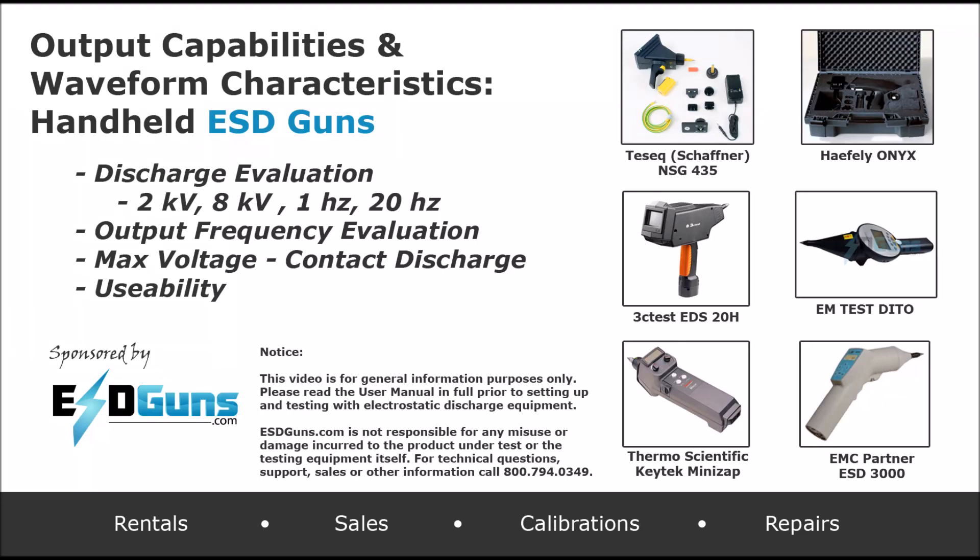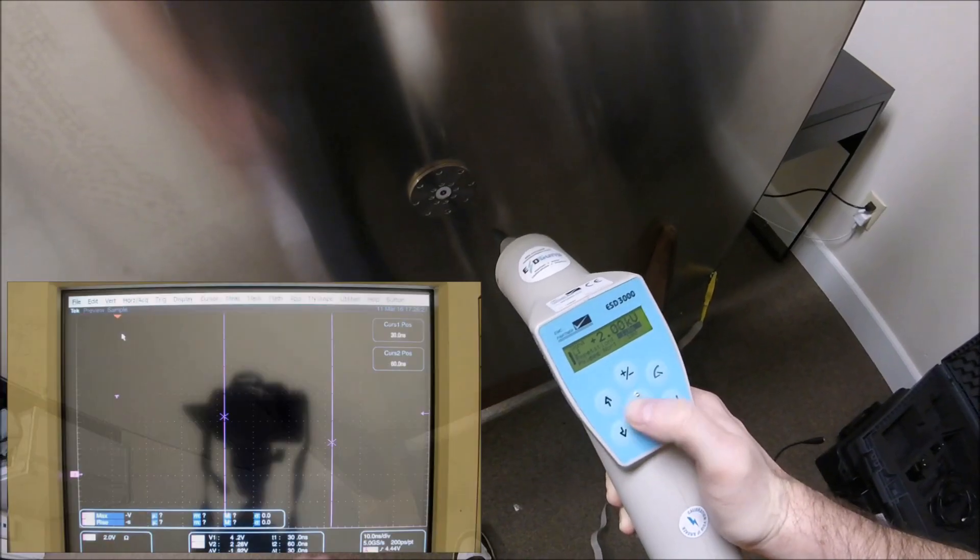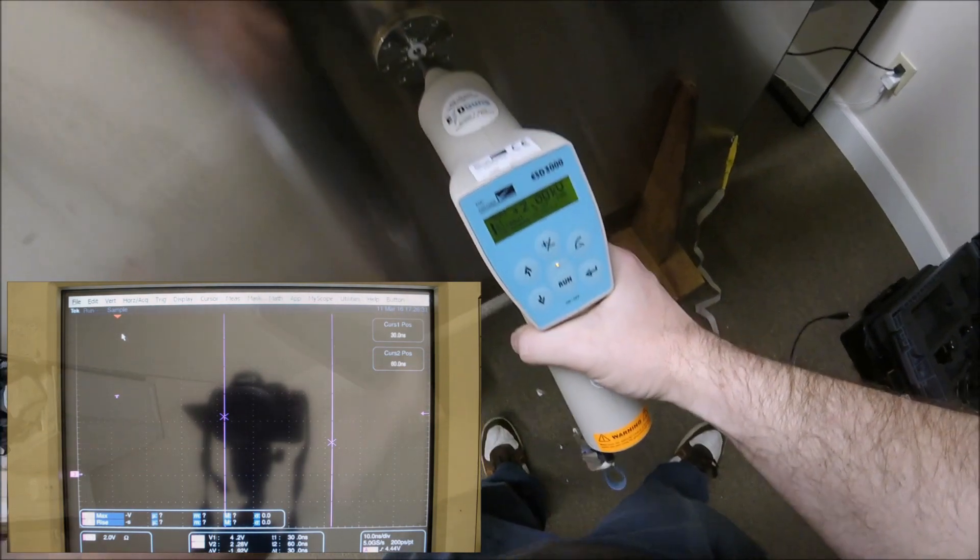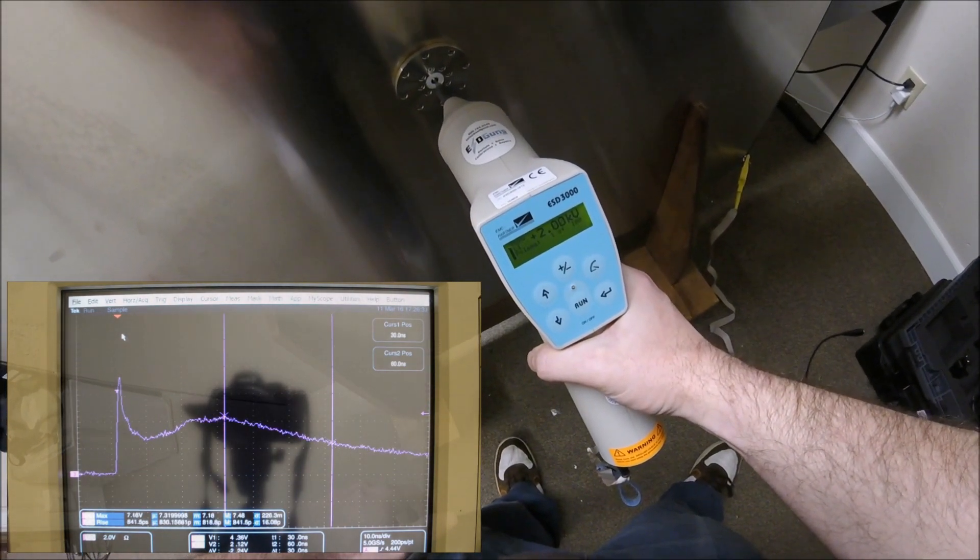We will discharge each simulator at 2 kV and 1 second intervals, reflecting level 1 contact mode for most ESD standards. We are going to let you make your own observations and determinations regarding waveform characteristics.